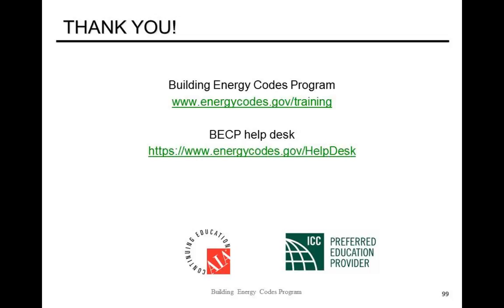The other thing, just to let you know, in terms of other reference documents, there's also a red line version of ASHRAE 90.1 that compares it against the 2013 standard. You can get that from the ASHRAE site. Another question I get a lot is about the efficiency tables, and whether they match the federal requirements. It's a complicated question because some of the efficiency requirements are what we call federally preempted. Some are not. For example, chillers are not under federal control, but rooftops are. We go to great pains to make sure these tables do align, and generally they do align.